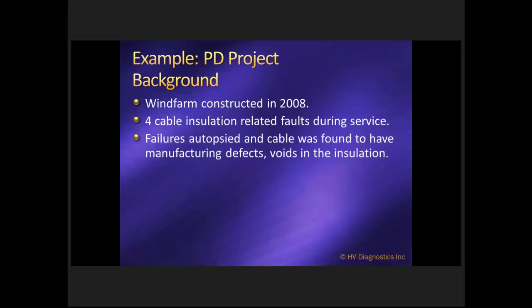The failures were checked, and the defects were found to be manufacturing defects inside the cable. And obviously with that, the customer was very concerned, so they asked us to do testing with the company to actually verify that the remaining cables in the ground were fit for service.